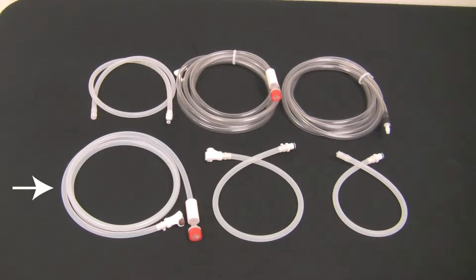The flush suction tube is used for suctioning detergent, water, and air. The umbrella foot valve filters particles from the detergent, water, and air before it is suctioned into the ScopeTech IQ. The ceramic weight is used to keep the umbrella foot valve weighted down below the water or detergent solution level.